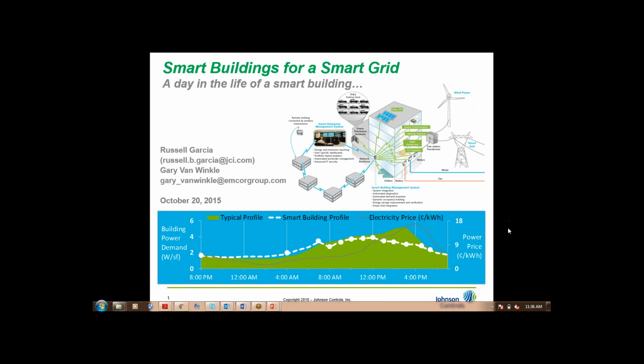So, can constant heating and cooling throughout the day and overnight end up costing just as much as a steady climate? I guess what you're referring to is a bit like when I was younger—I was always told it's cheaper to leave the TV on than to turn it off and on again because of the peak warm-up. It's most efficient to let the building drift at night to a pre-programmed level. In summer, if the building gets up to maybe 80 degrees at night, you might turn it on a bit to keep it from going above that. In winter, you might have a setting like 55 or 60 where you never let it get below that, so you can recover in time for it to be comfortable when occupants arrive.